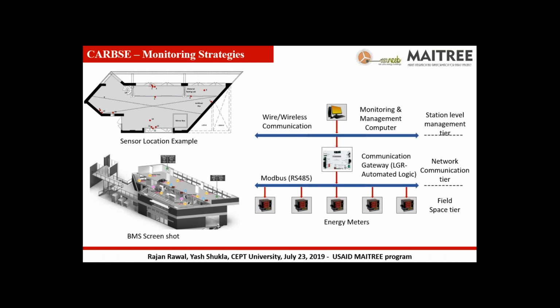The location of these sensors was also very strategically selected. You can see on the sensor location example screen that the red dots show the sensors at different points in the building, so that we can understand if one part of the building is overcooled while another part is hot, and you can identify cold and hot spots and accordingly control your air conditioning system. It was also linked with how the systems are placed. So if one of the systems was placed near certain points, you will have a sensor closer to it, so that you can control and modify the operation of the systems, and the impact of that will be immediately seen on the sensors.